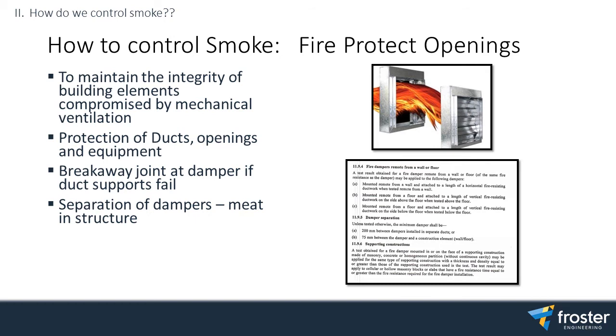Now, separation of dampers. If you have 2 small ducts running side by side in a brick wall, which is intended to be fire rated, it's 60, 60, 60, 60, so you have a 100 mil gap between the ducts and the dampers, the integrity of those penetrations is gone. How's the builder going to give you a clean cut with a 100 mil gap in brick? So that right there, if you see it on a design drawing, say it's on one of my drawings or another mechanical consultant's, you might want to voice it up and say that doesn't look right. You're squeezing it in a bit tight. So it's just taking a step back and looking at how do I maintain it, and how do we not compromise the integrity of the installation. You minimize those risks at the design table.